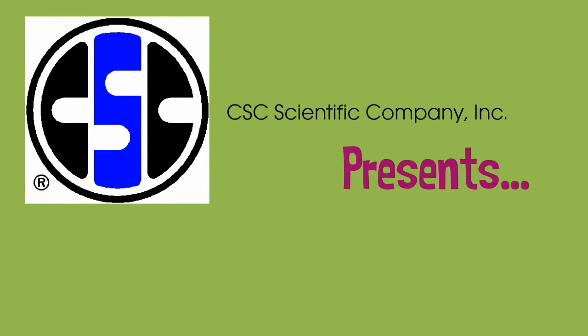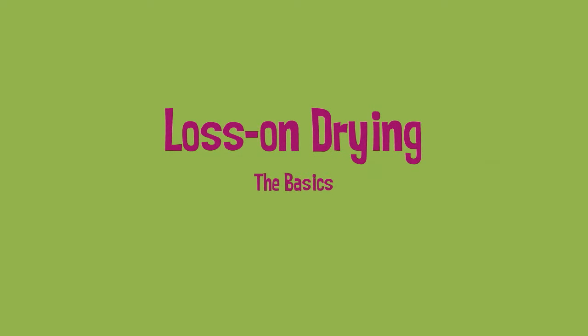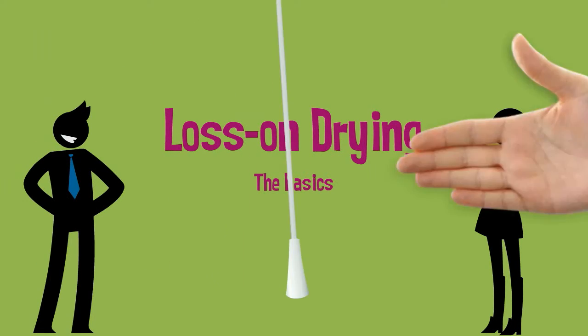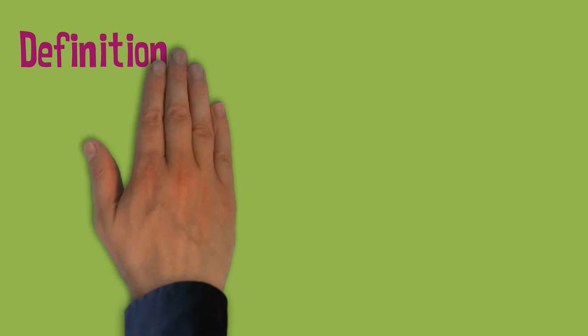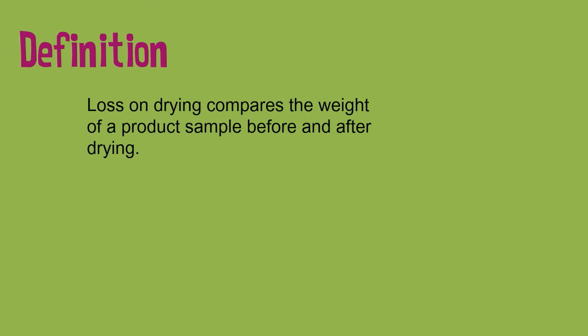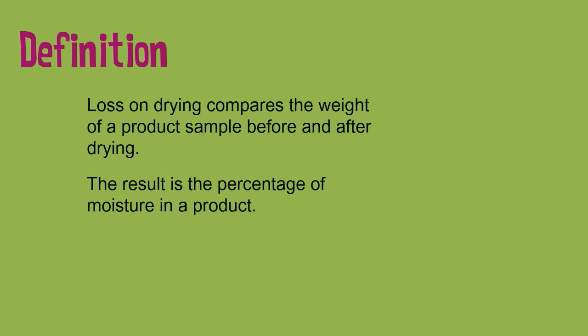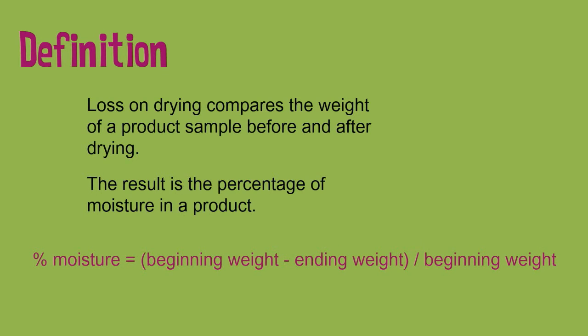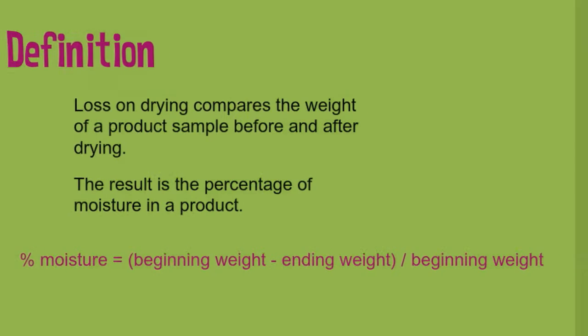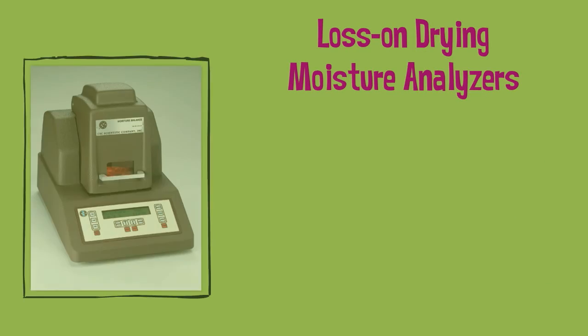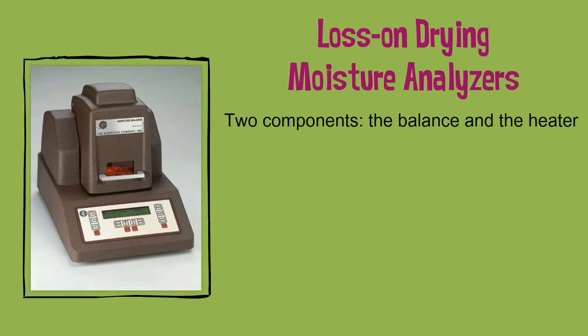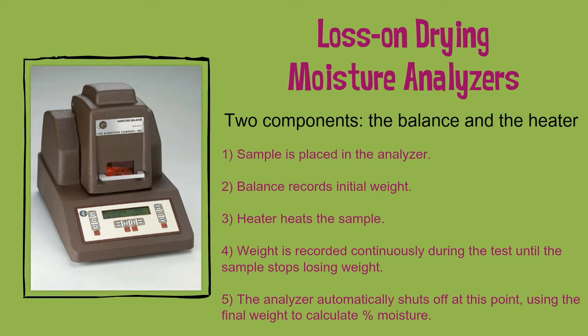Historically, laboratory ovens have been used to determine moisture content. The weight of samples before and after drying — sometimes as long as 12 hours — are compared and the percent moisture content calculated. This method is known as loss on drying, or LOD for short. The integrated moisture analyzer was developed to perform LOD testing in much shorter times: minutes, not hours.